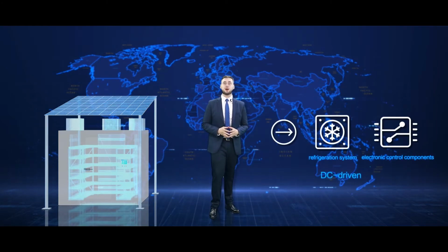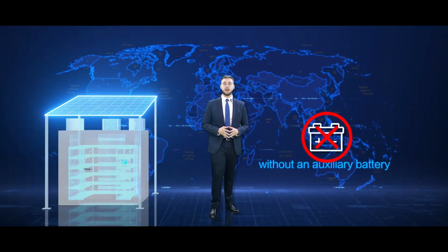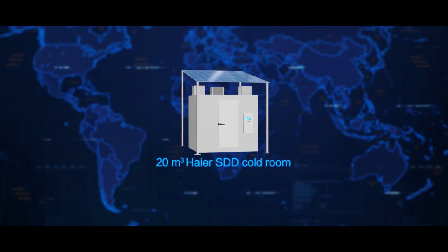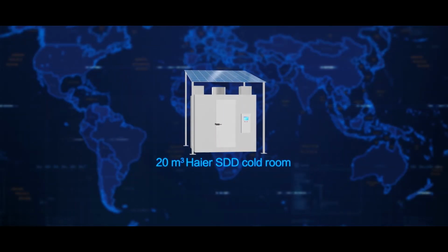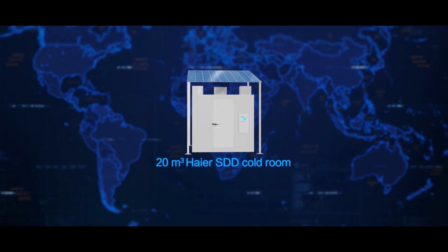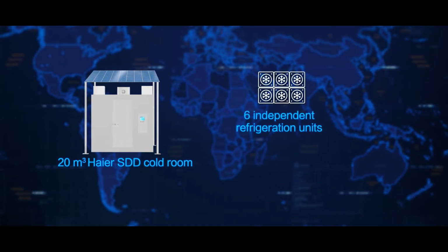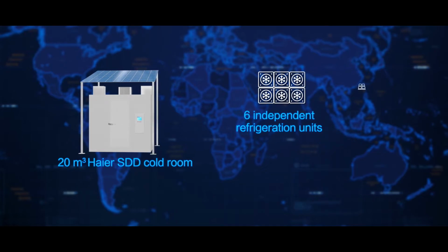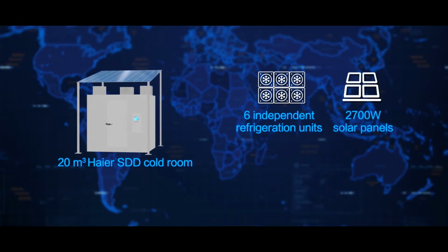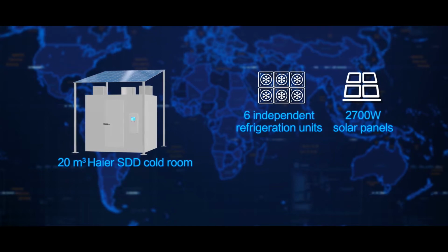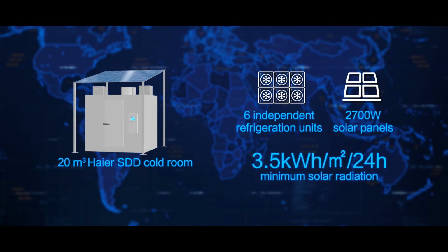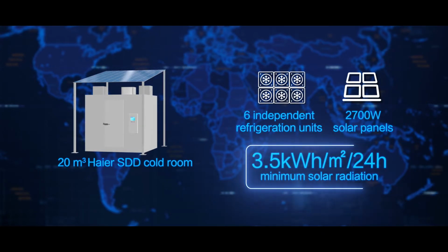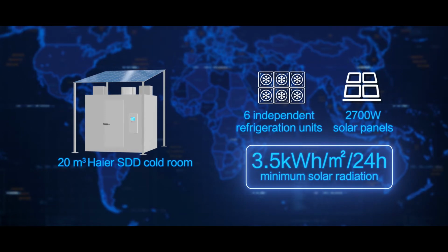The refrigeration system and electronic control components are all DC driven, and solar panels drive the refrigeration system directly without an auxiliary battery. For example, a 20 cubic meters Haier Biomedical SDD cold room in Nigeria, which is equipped with 6 independent refrigeration units and 2,700 watt solar panels, will operate normally under the minimum solar radiation reference period of 3.5 kilowatt hours per square meter every day.